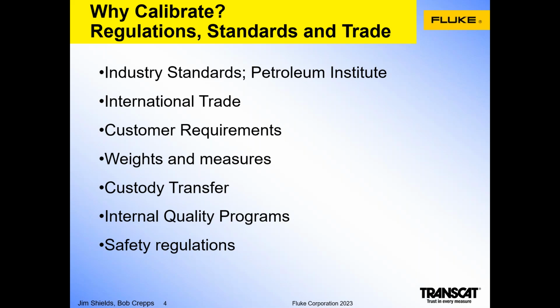So why calibrate? Reasons to calibrate. Well, when I'm talking to customers that are engaged in this process, the primary reasons are the regulations that dictate practices within industry, the standards that are applied to various vertical organizations, and of course, some calibrations are a requirement for trade. Examples of an industry standard, for example, the Petroleum Institute is an industry standard. The Petroleum Institute, for example, maintains procedures and practices on a voluntary basis that puts companies in compliance with the more daunting regulatory agencies that are often auditing the industry.